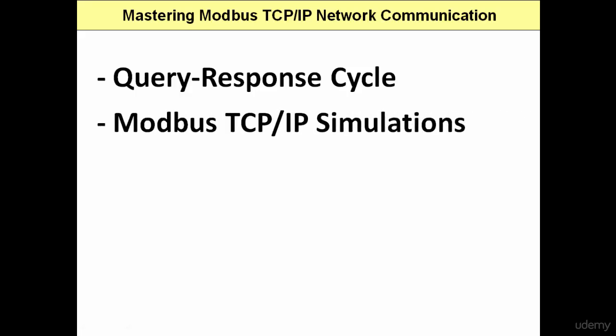Then we have Modbus TCP/IP simulations. This is the fun part. We are going to use ModScan32 and ModSim32 Modbus simulators on a laptop so we can see the Modbus data streams live for various query response cycles. You can have read input registers, read holding registers, read coils, preset single register, all of that we'll have a look at. By doing this, you'll be able to troubleshoot network communication problems. If you can recognize data streams, then you can recognize problems with the data streams.